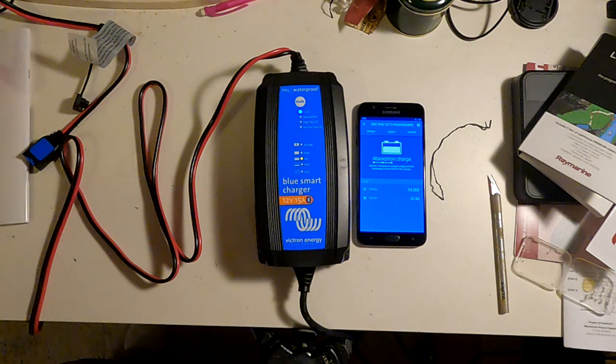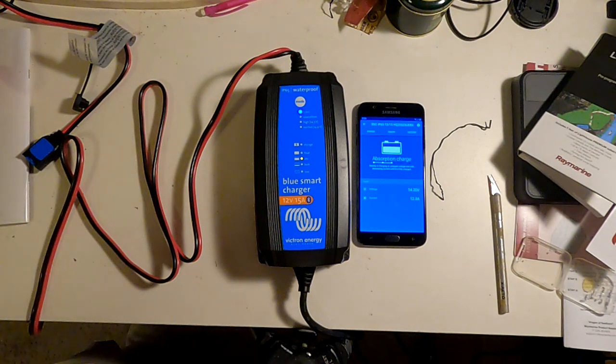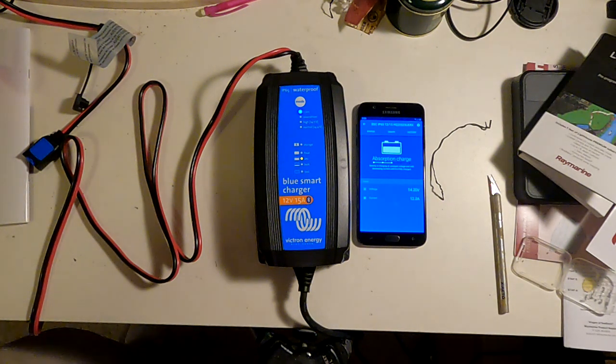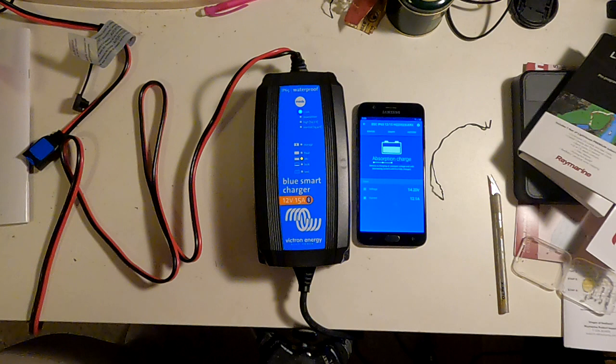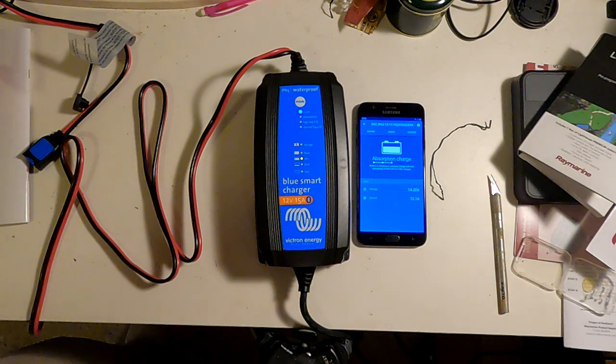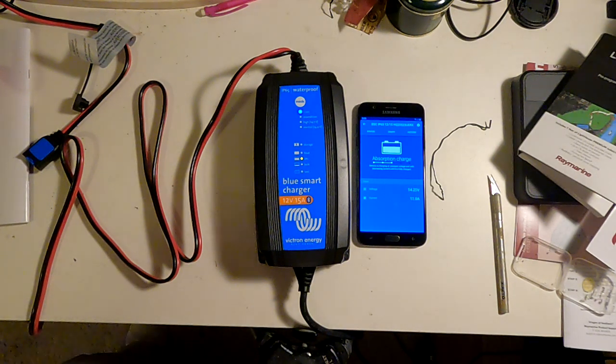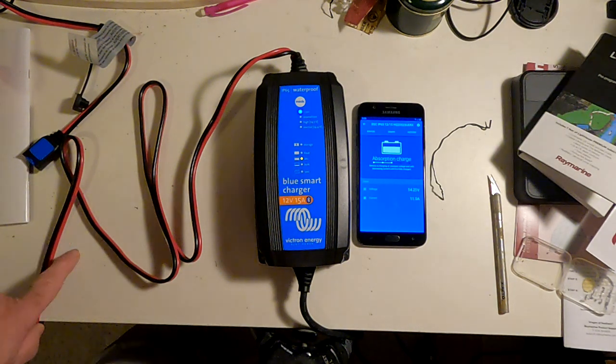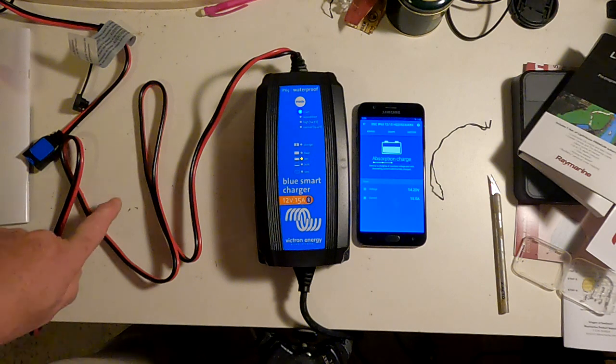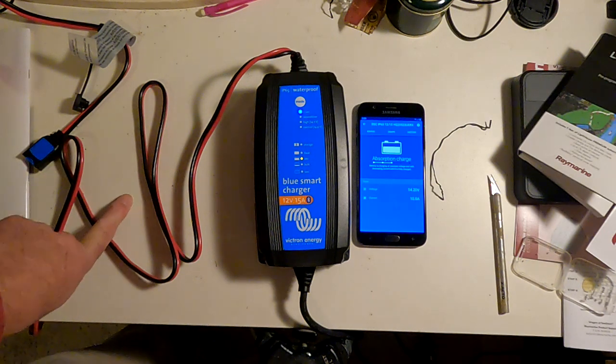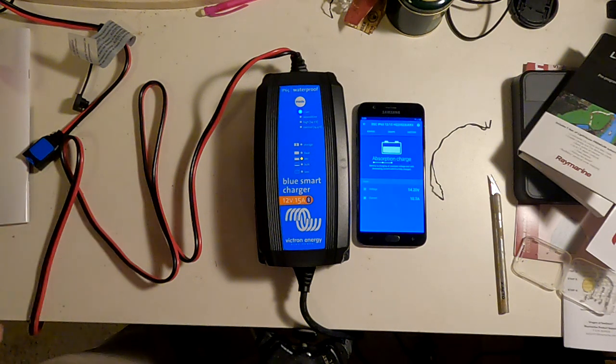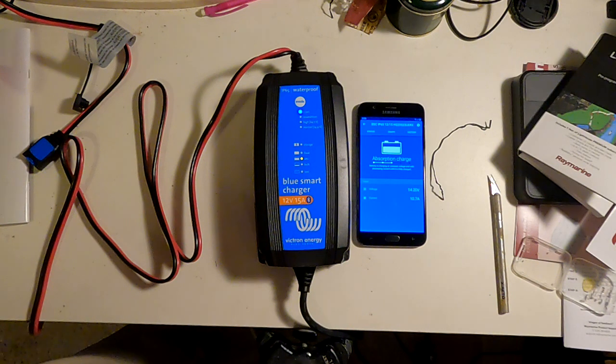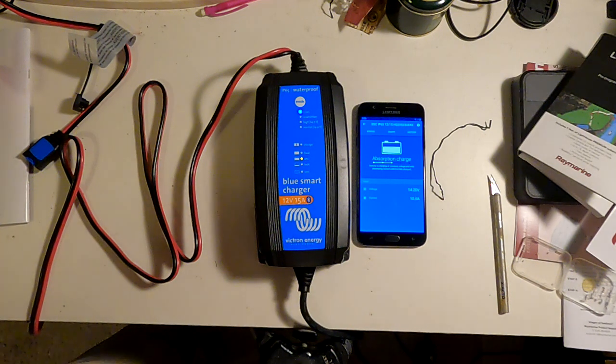The absorption charge depends on how depleted the battery was in terms of how long it lasts. If the battery was not particularly depleted, it should last approximately half an hour. And if the battery was drawn way down, it could last as long as eight hours.